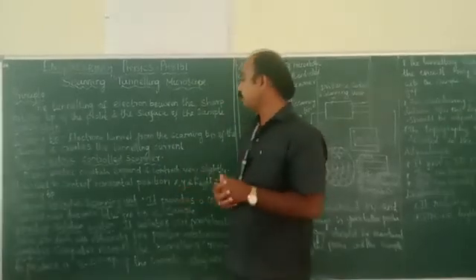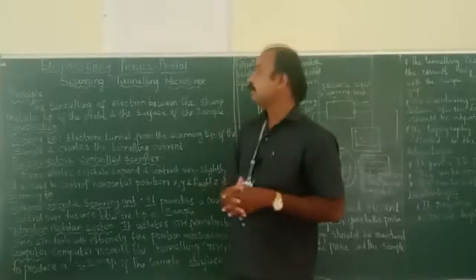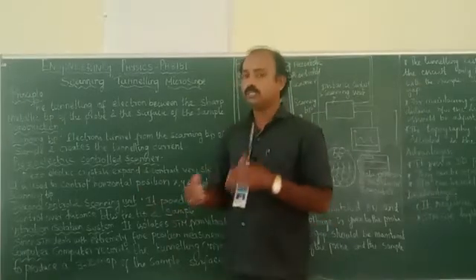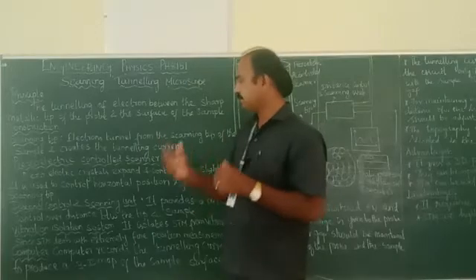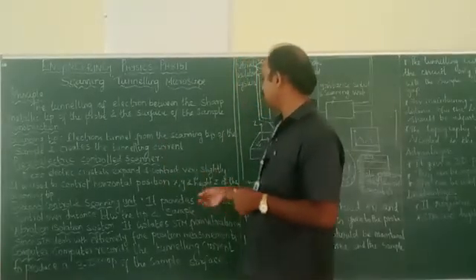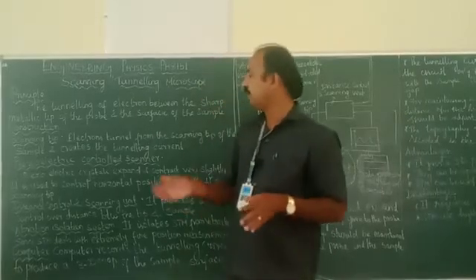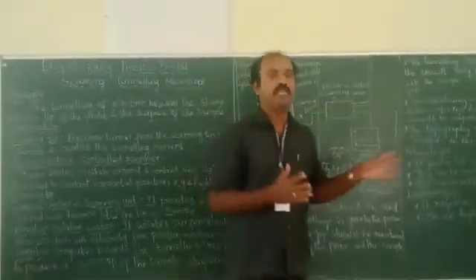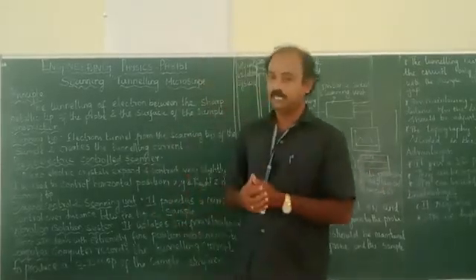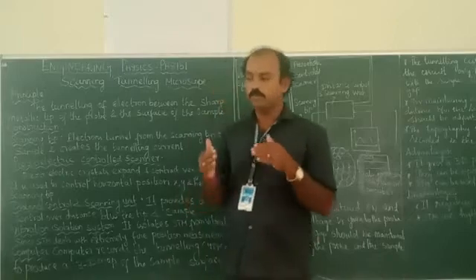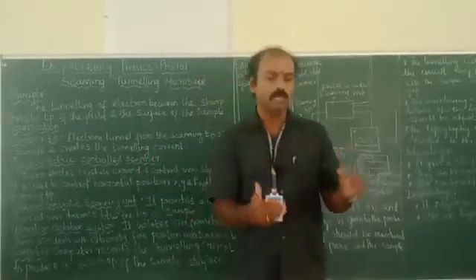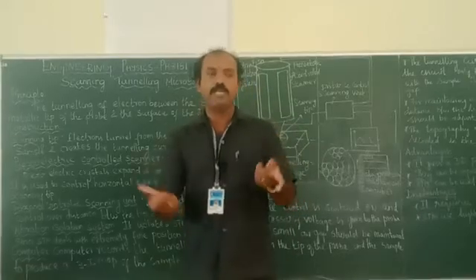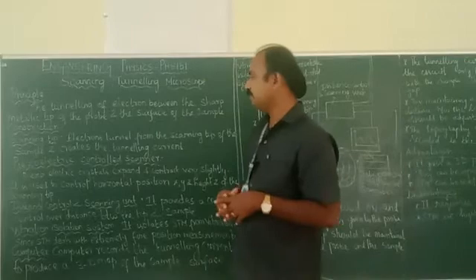The piezoelectric controlled scanner is also a part of this microscope. The piezoelectric crystal expands and contracts slightly due to the application of pressure and external force. It is used to control the horizontal position — x, y — and the height z of the scanning tip, so the scanning tip can move in x, y, and z directions in order to get a three-dimensional image of the surface being detected.